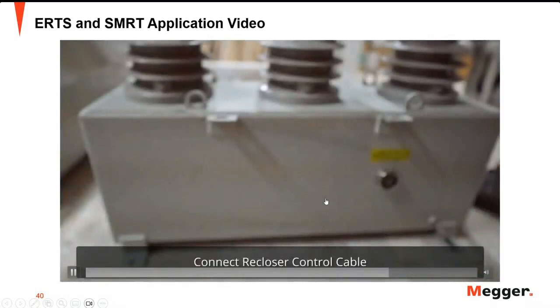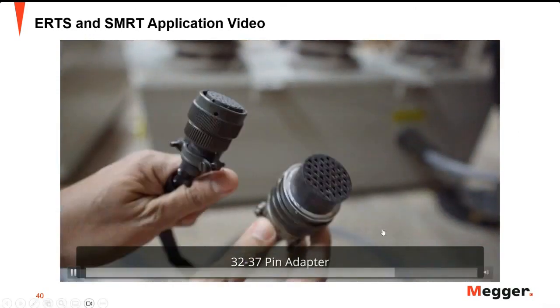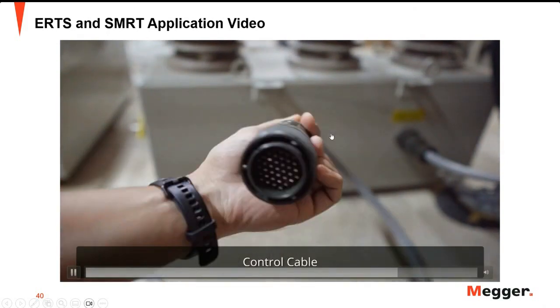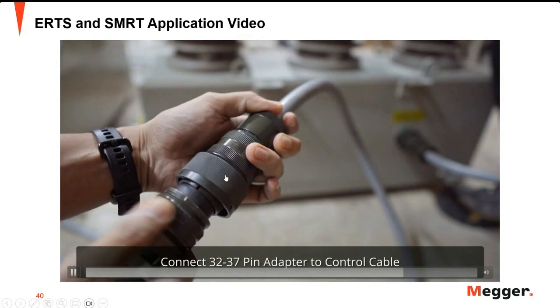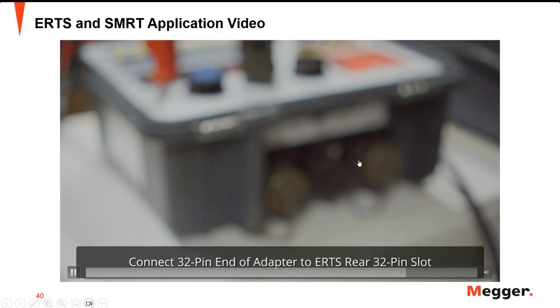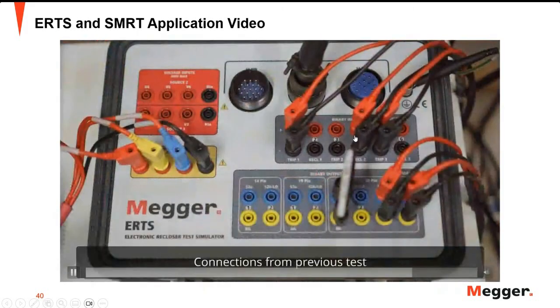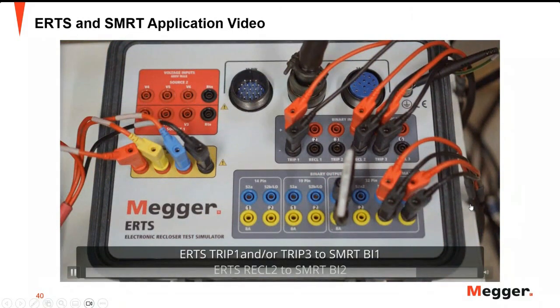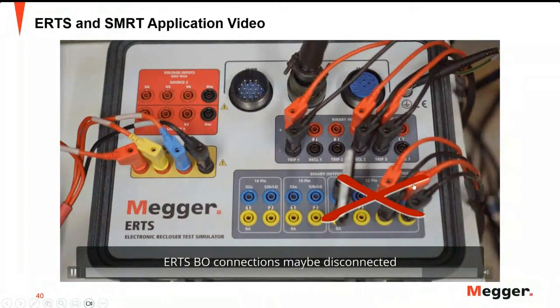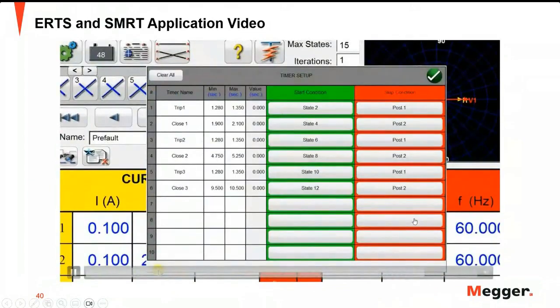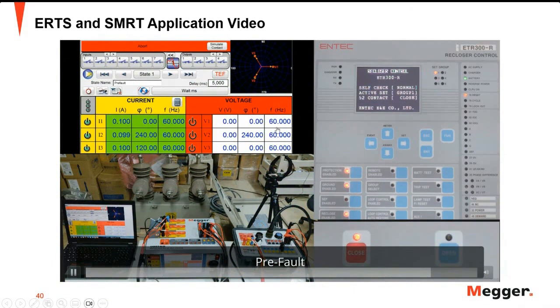The next step is testing the recloser unit and the control unit simultaneously. We will connect the cable to the recloser connections of the ERTS. First we need to use this adapter again since it is a 32-pin connector — we need that adapter to fit into our ERTS. We can remove the previous connection and connect it to the recloser connection. Since the recloser unit is now connected, it's possible to remove the connections going to the SMRT.